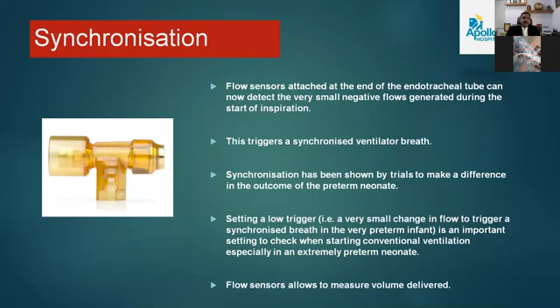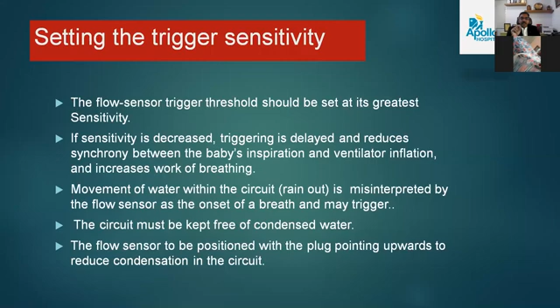One thing you should always be aware of is that when you are doing triggered ventilation, avoid water within the circuit, because this may get misinterpreted by the flow sensor as the onset of a breath, multiple triggering may happen, and it may lead to asynchrony. The circuit should always be kept free of condensed water. The flow sensor should always be positioned with the plug pointing upwards. This is one of the tricks which has been recommended to reduce condensation in the circuit.